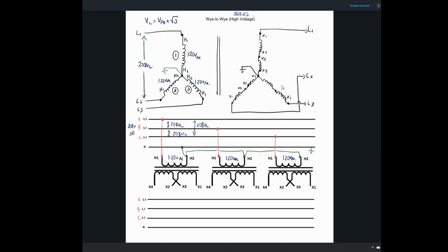So all the 4s are being tied together on the secondary, and in order to get the higher voltage out of those secondary windings, we're going to series up 2 and 3. And we saw on the previous diagram that because the ratio is 1.73 to 1 between the primary and the secondary, if I have 120 volts on the primary, that means I'm going to have 69 volts on the secondary windings here. Okay, so we'll throw that into this diagram right here.